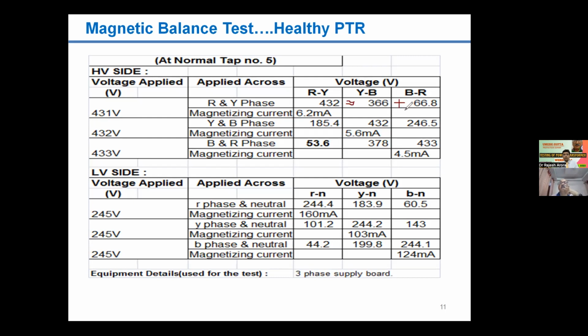when we are injecting voltage in one winding through terminals RY, 432 volt, the total of the two voltages, 366 and 66.8 volt, should be equal to the voltage which we are injecting in the winding. Similarly, for the other two windings, the tests are repeated. But as I discussed earlier, when we inject in the central limb, the distribution will be symmetric or nearly symmetric in the two outer limbs.